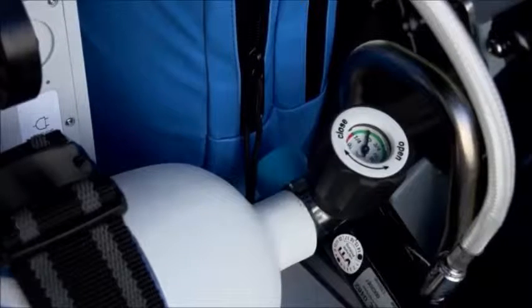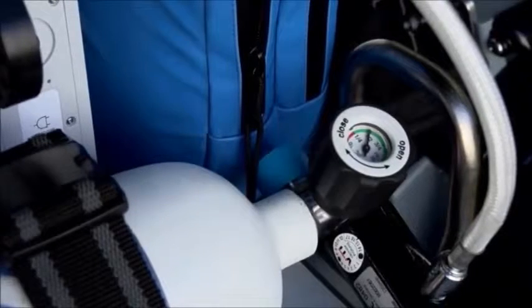A source of pressurized gas must be used with the system, in either oxygen or breathable air, at pressures from 3.1 to 4.8 bar, 45 to 70 psi, with a minimum recommended usage pressure of 3 bar and a flow rate of 60 liters per minute.